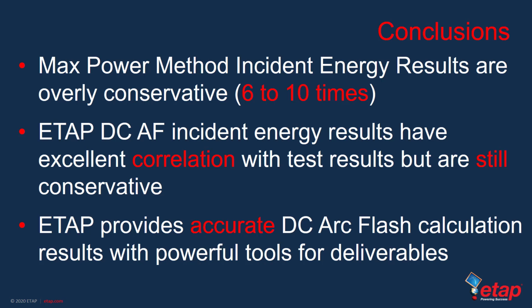In the world of DC arc flash, in reality, I would say that 80% of the accuracy is in the actual estimation of the bolted DC short circuit current, and the remaining 20% is actually in the equations that we use to estimate the DC arc current, resistance, and incident energy. The modeling algorithm needs to account for the different types of sources. Like Raghu showed in his presentation, ETAP not only produces accurate results, but also has very nice features and tools to save analysis time and to help us deliver the results to the end consumer of an arc flash analysis.